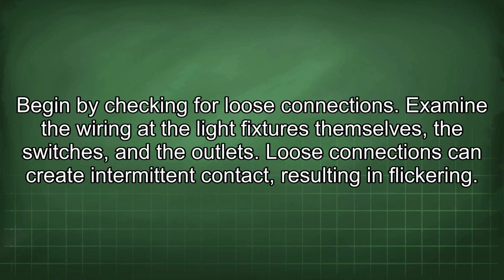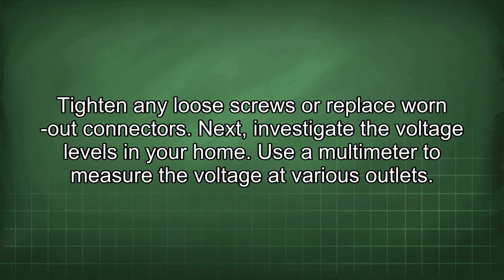Begin by checking for loose connections. Examine the wiring at the light fixtures themselves, the switches, and the outlets. Loose connections can create intermittent contact, resulting in flickering. Tighten any loose screws or replace worn-out connectors.